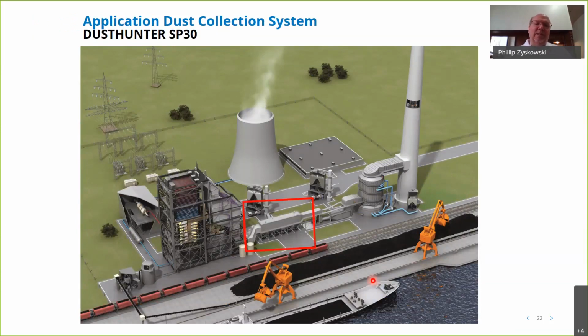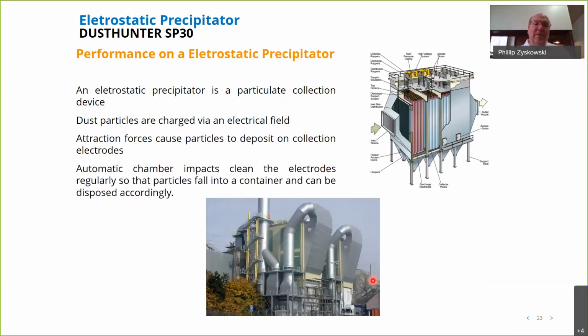Got your dust collection system here. This is a rendering of a typical electrostatic precipitator. The Dust Hunter on this application, we would imagine being installed in this ductwork here on the exit. And really, the only control that could be realized would be maybe your rapping sequence. We found early on when we developed the wet PM CEMs that often the rapping sequence for the ESP was way out of sync, and this caused excursions well above emissions permits. So we would envision the Dust Hunter alerting you of that before it became a problem further down the line.